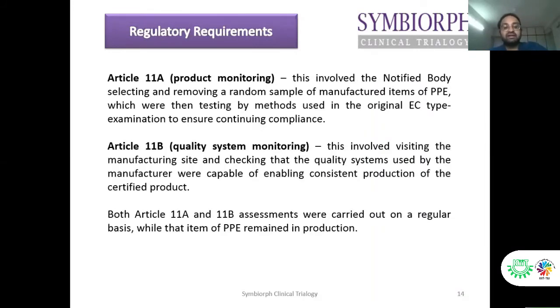Now, as per the regulatory requirement, for Module C2 and Module D, an on-site audit will be carried out by the notified body. As per Article 11A, two types of audit can happen: either a product monitoring activity or a quality system monitoring activity, carried out by the notified bodies.